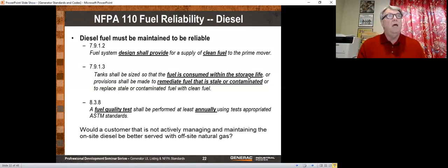If that water gets high enough to reach the input of the generator where the fuel is sucked up into the generator, and that's typically 1 to 2 inches above the bottom of the tank. Once you start sucking water, your generator is not going to work very well.